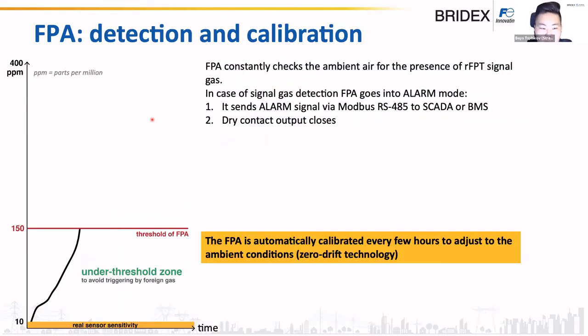So the principle of working is that the FPA constantly checks the ambient air for the presence of signal gas. The FPA is very, very sensitive. The real sensor sensitivity is 10 ppm. The ppm is parts per million, the concentration. But we use an artificial threshold on the FPA, just to avoid triggering by some foreign gas. Let's imagine you are in a chemical plant, where there are some gases in the ambient air. Just to be sure that we don't misoperate, we use the threshold of the FPA.